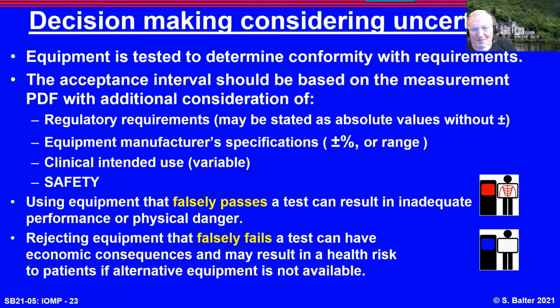So here's decision making. We test for conformity with the requirements, look at the regulatory requirements, and very often regulatory requirements are absolute. The half value layer shall be greater than 2.5 millimeters of aluminum. The maximum radiation output shall be less than 100 milligrays per minute. These are stated as absolute values without any uncertainty. The benefits, presumably, of being a regulator.